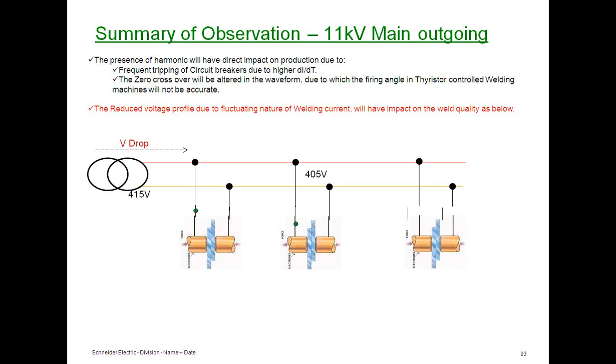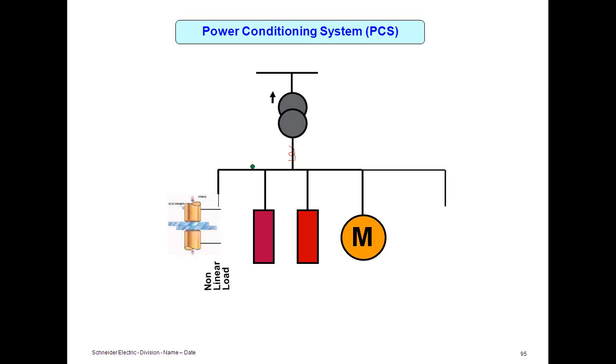So we discovered the reason is a huge fluctuation of load that was only for 10 to 11 electrical cycles, about 0.2 seconds. This fluctuation of load was creating voltage flickering and was creating a lot of impact on the quality of weld objects. So the solution for this case was to have a centralized power-conditioning equipment that can take care of harmonics, that can take care of huge load fluctuations, and the problem was solved.